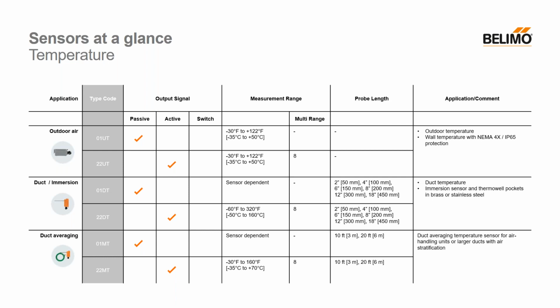One thing I like to say about this is where we really focused on the complication of installing a duct averaging sensor. For those of you who've been in the field and had to roll out that copper or aluminum capillary tube, make sure it didn't get damaged, fish it in the ductwork, harness it around the coil and make sure it didn't get kinked, you know that's a process. That can be a time-consuming and relatively difficult and labor-intensive process.